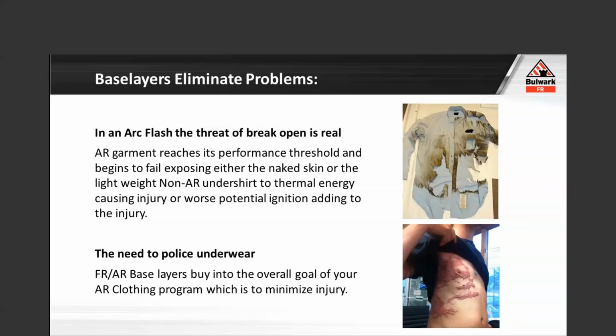Well, if I'm a little bit closer and that equipment decides to clear in 8 cycles instead of the 2 to 4 that it was calculated at, could I be exposed to greater incident energies than expected? Yes, you can. Can that outer layer start to fail? Yes, it can. What's underneath now may potentially contribute to injury by what? If it's cotton, it's latent fuel. Is there enough incident energy after breaking the outer layer open to potentially cause ignition? We have seen it. So how do we eliminate that? The next layer underneath also has FR properties, and we take that out of the equation.